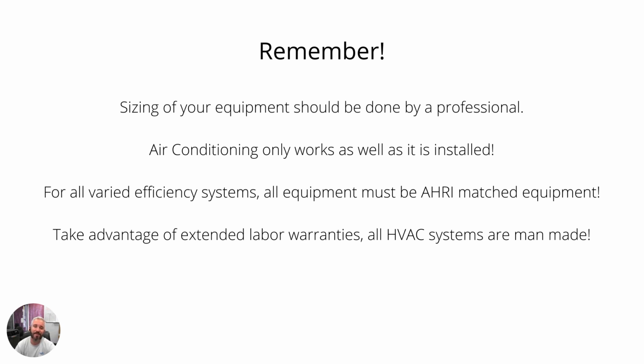Remember, sizing of your equipment should always be done by a professional. We use what's called Manual J load calculations, and this actually tells us exactly, by the science, not by a guess, how many BTUs your system is required for heating and for air conditioning. When we perform an estimate, even on a retrofit system, when we're replacing existing equipment, we still want to check the duct sizing and the Manual J load calculation on the house. And if we're building a new duct system, we have to do a Manual D calculation, which shows us the sizing of the ductwork, and then the Manual S will tell us exactly what size system to attach to that duct system. So it's pretty cool.